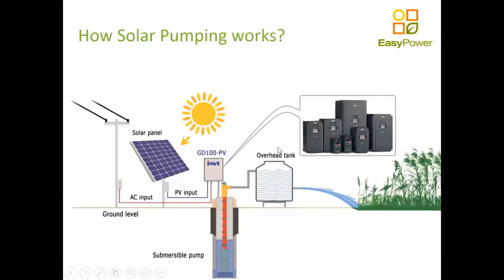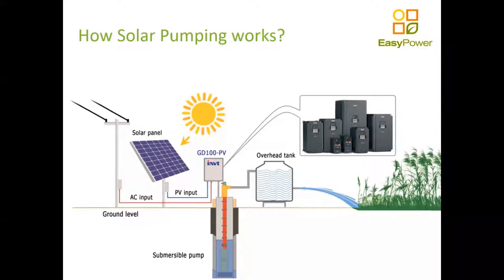In a nutshell, this schematic shows the main components of a solar pumping system. The first is obviously the solar panels — we need power generated from the sun. This is fed into the pump inverter. The pump inverter is, in essence, a 3-in-1. First, it is an inverter — it produces AC power, both single phase and three phase, from a DC power supply. Secondly, it's a rectifier — it takes power from the grid and feeds it to the inverter so the inverter can feed it out at a different frequency.